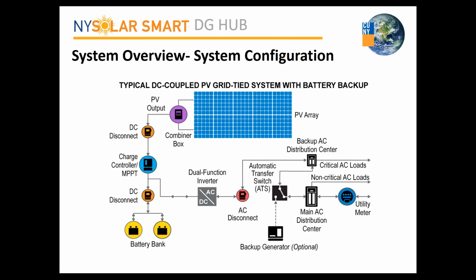And during off-grid mode, when you're islanded, you can have a backup generator. The automatic transfer switch toggles down to the generator that would feed the critical load and could also be used to charge the batteries through that dual function inverter. This is a nice system in that it's more efficient, you have one inverter, you use the PV to charge the batteries directly, and there are fewer communication complications for dispatching. But if you already have a grid-tied system, it often takes more changes in wiring to redo this. This configuration is really good if you're putting in a PV system and batteries at the same time. It's higher efficiency in this way.